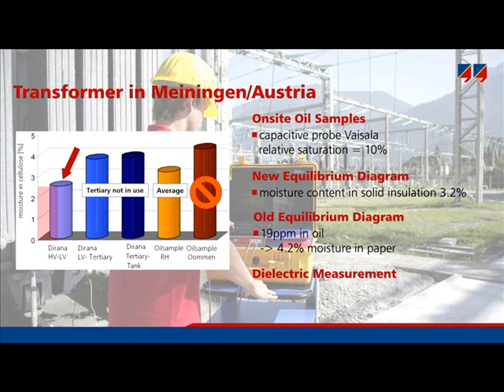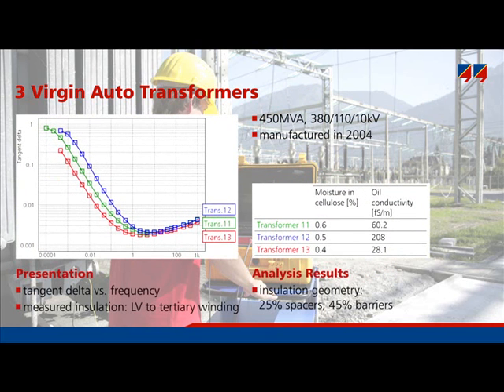The last example concerns three new auto-transformers. The measurement was made in the factory just after they were manufactured. This graph shows the dissipation factor of all three transformers — they all have dry insulation values between 0.4% and 0.6%. This example illustrates that a dielectric response measurement can also check the quality of the production process in a transformer factory, proving that the evaluation is just as applicable to new transformers as to old ones.